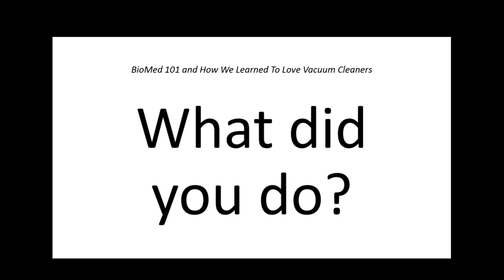N95s. I've had to go in for a few service calls because now what they're doing is, for the isolation, the patient would stay in the room. Now it's worse because that patient might be on dialysis any time of the week and isolated. So if the water system goes down, leaks, or the machine has a problem, they don't want to take that out of the room, which makes it difficult because now they have to respond and go do something, tighten a clamp or plastic, whatever it is. So I have to go through. The last 3 months, once a month or so, because they're keeping that equipment in there.